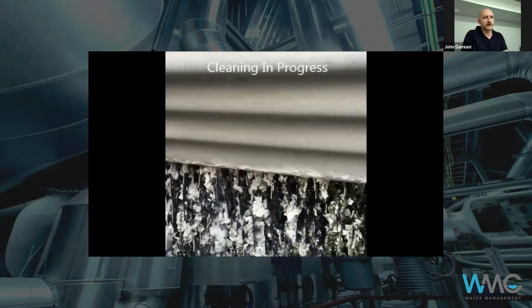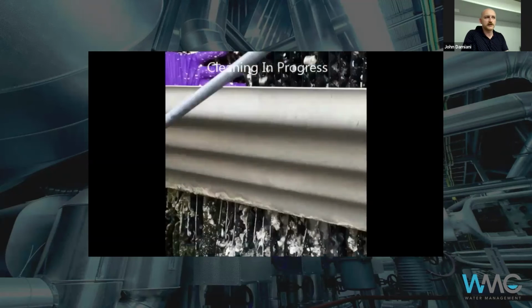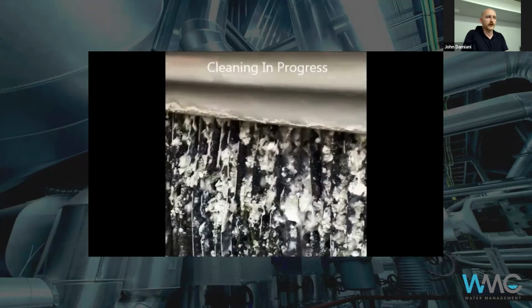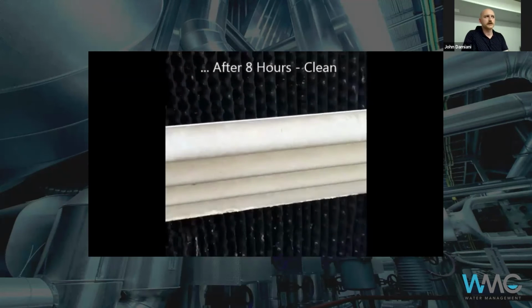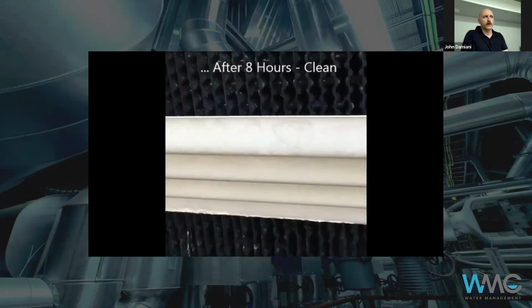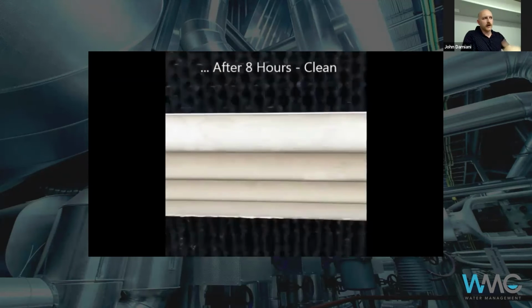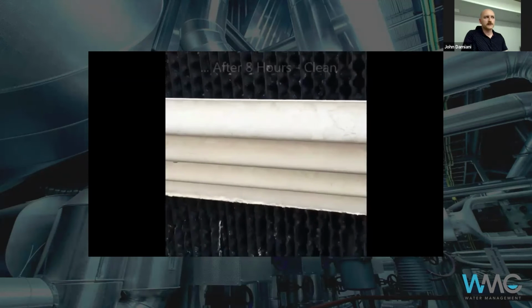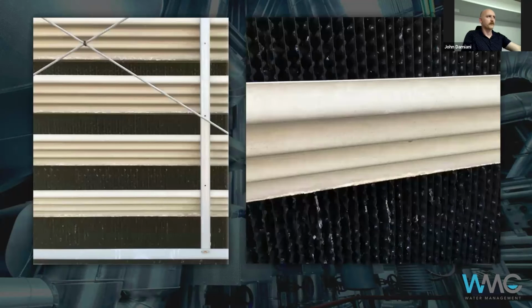This is an 8-hour cleaning that we ran. The cost isn't low because you've got probably 2 or 3 guys on site for 8 hours, plus all the product we have to use, but we can get it clean, as you can see, and that's online while the system's running. As we pull those deposits off, you get a lot of efficiency back. You can see some of the casing of the cooling tower has been scaled, and who knows what kind of corrosion damage there is elsewhere in the system. But as far as the fill, we can get the system back up online and running.